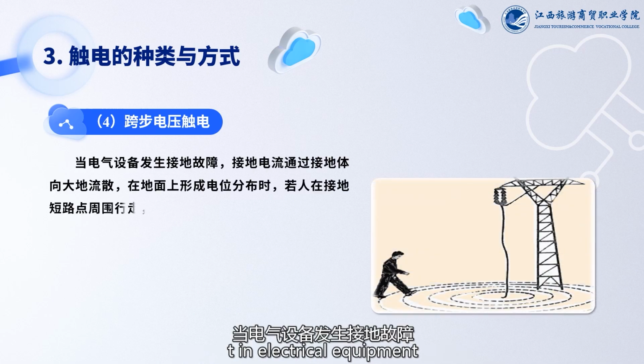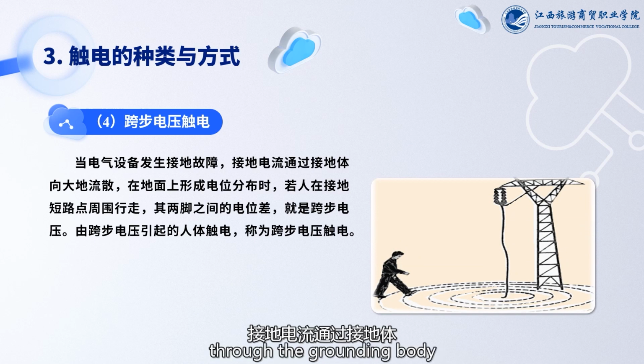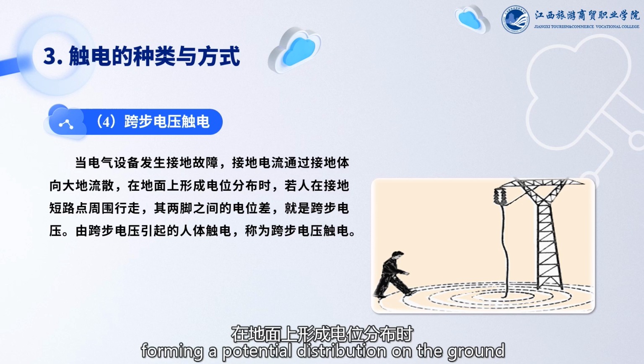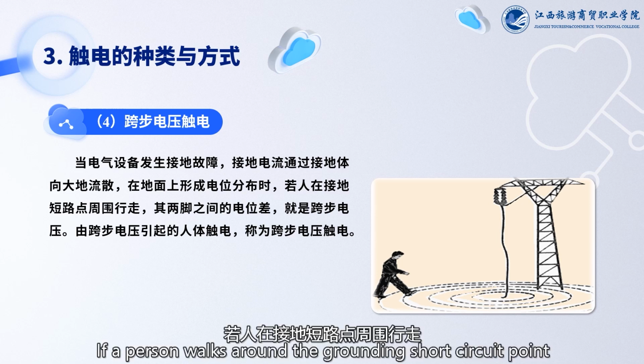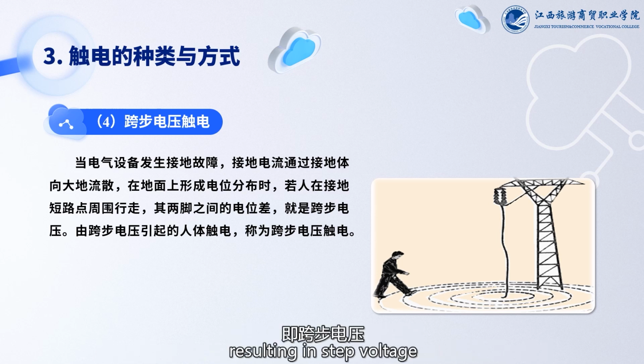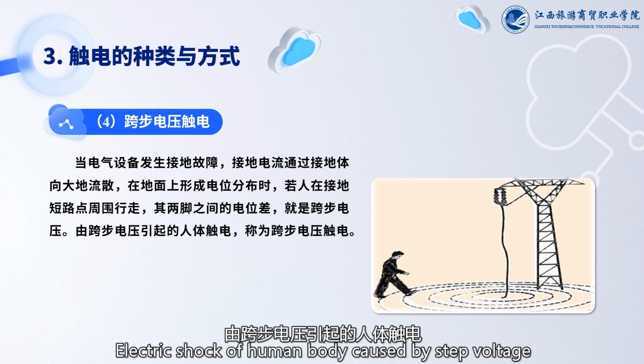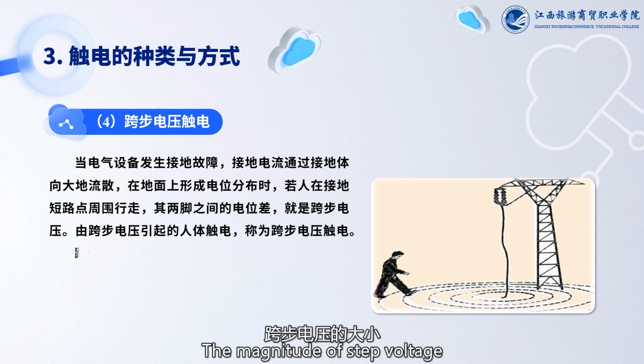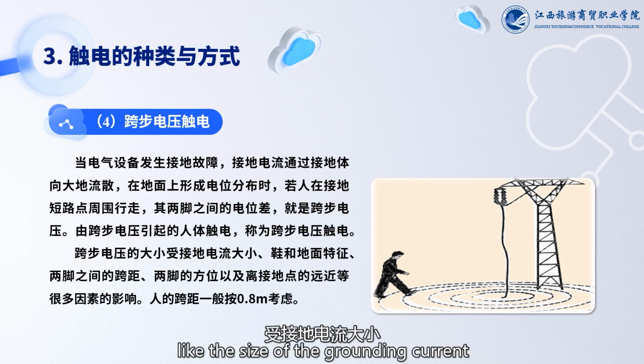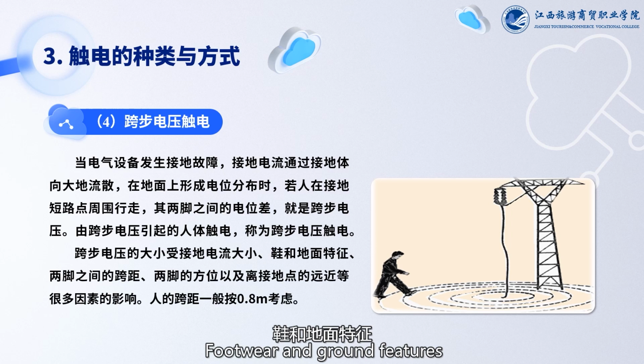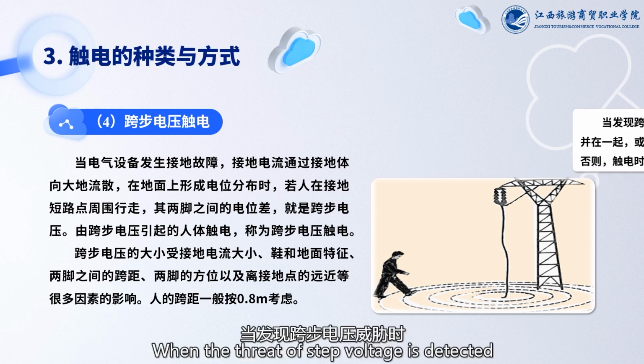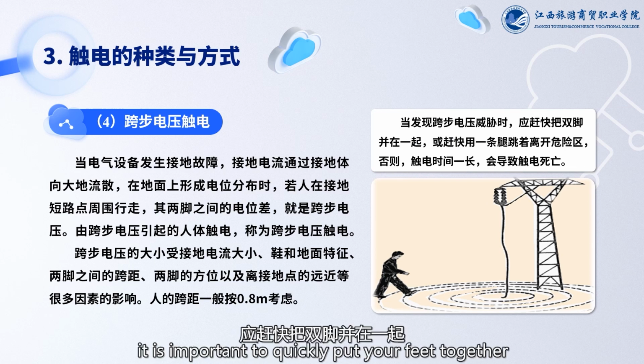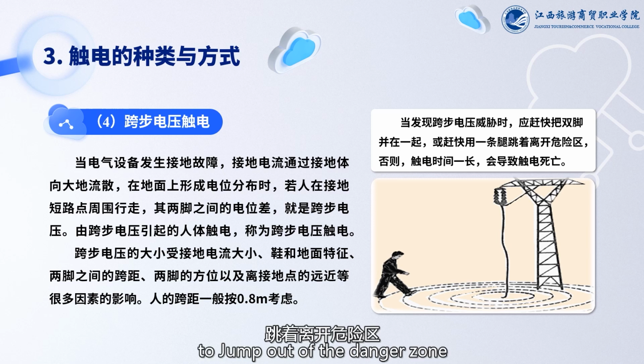and eyes. Step voltage electric shock occurs when there is a grounding fault in electric equipment, and grounding current passes through the grounding body, scattering to the earth, forming a potential distribution on the ground. If a person walks around the grounding short circuit point, there is a potential difference between his feet, resulting in step voltage. Electric shock of human body caused by step voltage is called step voltage electric shock. The magnitude of step voltage is influenced by factors like the size of the grounding current, footwear, and ground features. The span between 2 feet, the orientation of 2 feet, and the distance from the grounding point. When the threat of step voltage is detected, it is important to quickly put your feet together or use one leg to jump out of the danger zone. Prolonged exposure to electric shock can lead to electrocution.